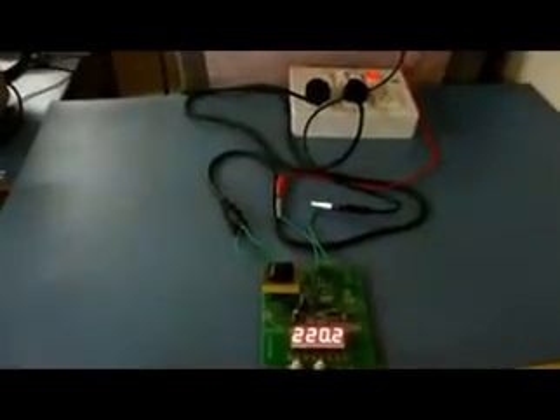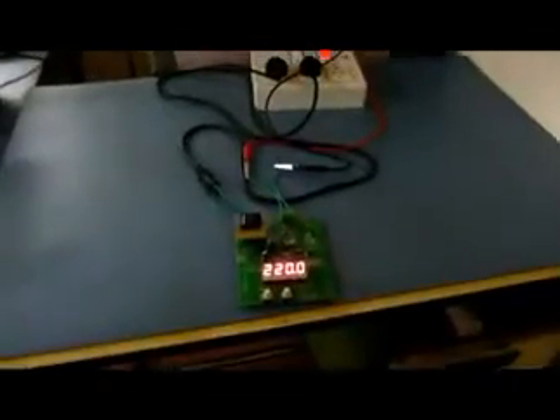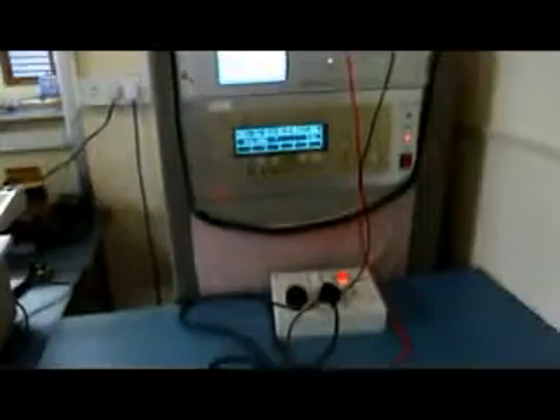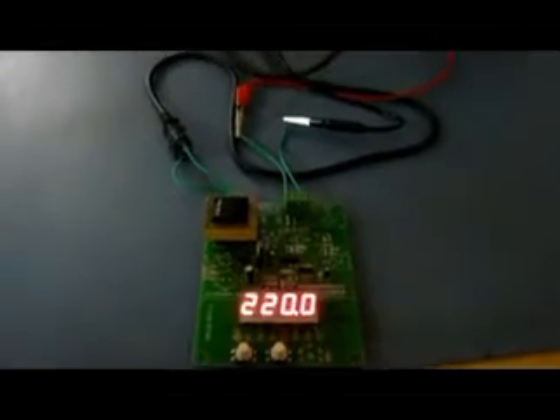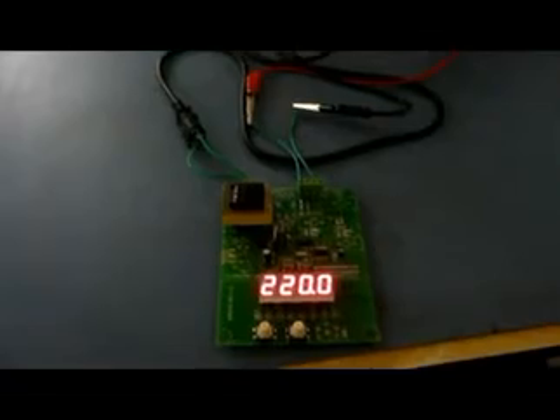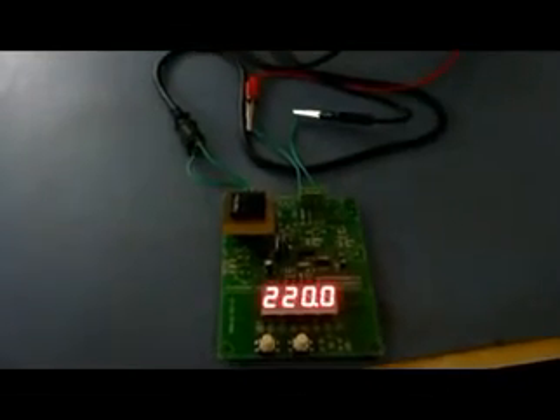We'll now make it to 54 Hz. So we have 53.999, and the DPM still reads the same voltage. We'll now move to 58 Hz. Our source has settled to 58 Hz, and we are still reading 220. You can see the voltage on the source is now 219.9, for which we are reading, and it is fluctuating between 219.9. Then you go to 62 Hz.